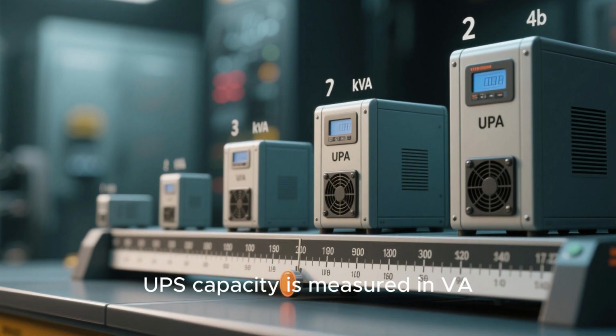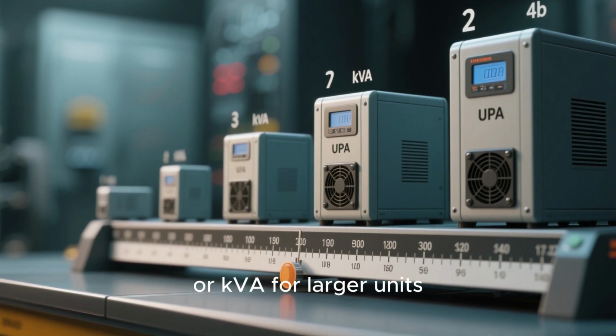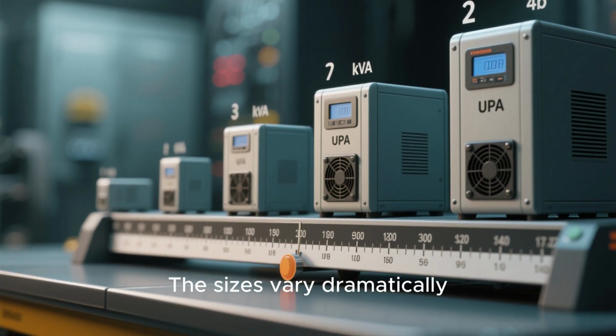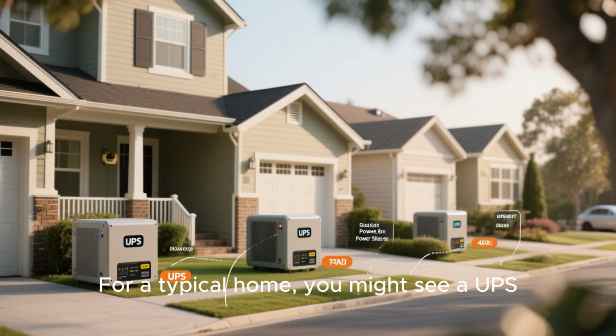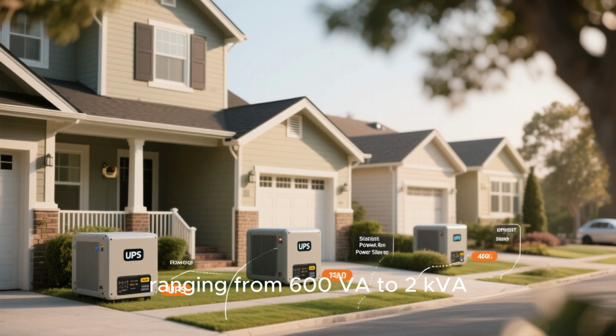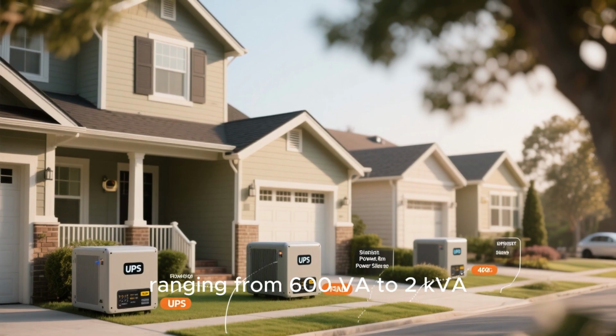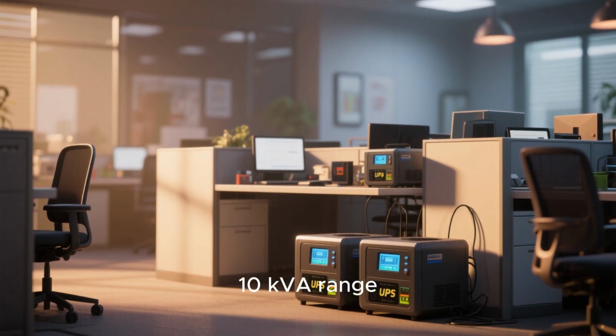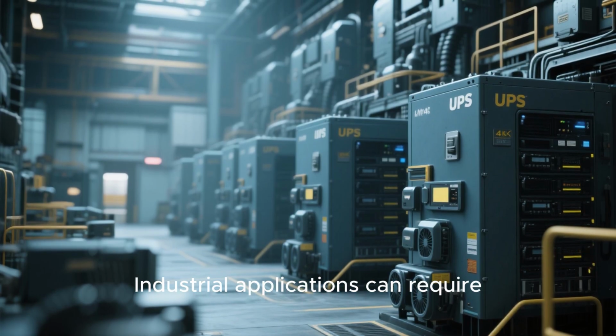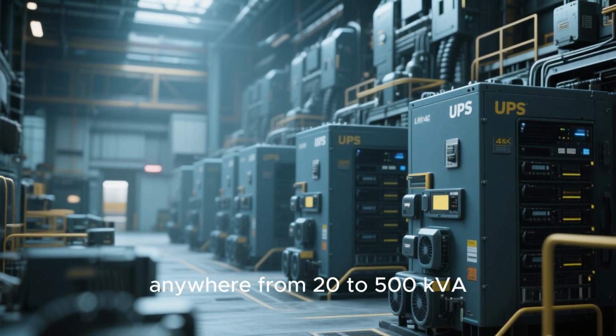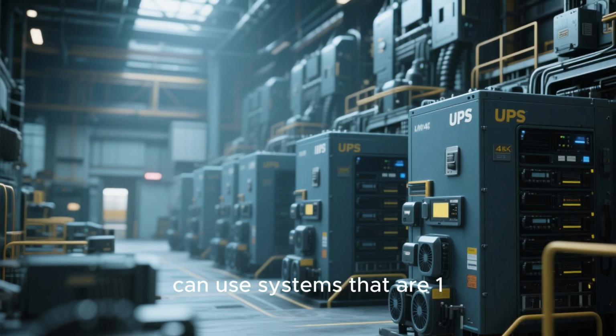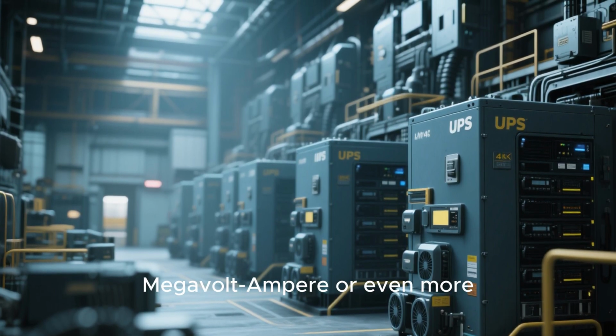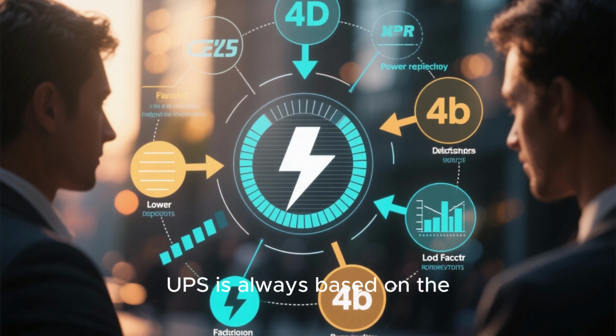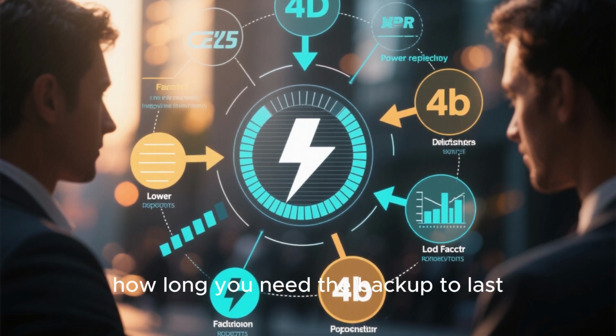Now let's talk about capacity and ranges. UPS capacity is measured in VA, which stands for volt-ampere, or kVA for larger units. The sizes vary dramatically depending on the application. For a typical home, you might see a UPS ranging from 600 VA to 2 kVA. A small office might need something in the 3 to 10 kVA range. Industrial applications can require anywhere from 20 to 500 kVA, and massive data centers can use systems that are 1 megavolt-ampere or even more. The right size for a UPS is always based on the total power your equipment needs, how long you need the backup to last, and the power factor of the load.